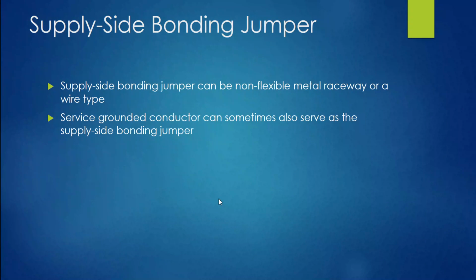All right, so size. The supply side bonding jumper can be a non-flexible metal raceway like rigid, IMC, rigid metal conduit, EMT, or the wire type. Obviously we have supply side bonding jumpers of wire. We do that all the time. A lot of our examples here are going to be supply side bonding jumpers of the wire type, connecting the enclosures to these different raceways. For example, we showed an open bottom switchgear in that example. Now, the service grounded conductor can sometimes also serve as the supply side bonding jumper. Yes, and we're going to see that application in 250.142 shortly, where it bonds all of the enclosures and everything together to the grounded conductor, which is perfectly acceptable on the line side or supply side of the service disconnecting means.